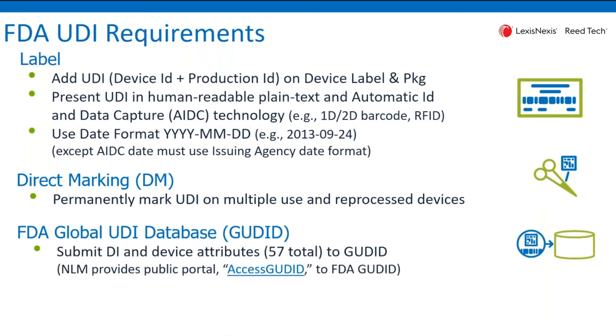There are requirements to report the device identifier — this is not the production identifier. This is just the first portion, the device identifier, and a number of attributes. Totaling 57 attributes are reported to the FDA's global UDI database, GUDID.